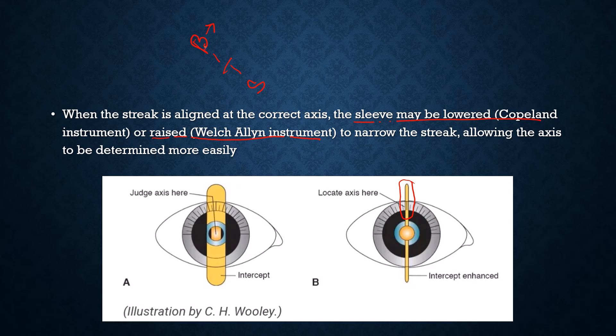To summarize using BITS: there will be no break when the streak is aligned with the reflex; the intensity will be brightest when properly aligned; the beam will be thinnest when nicely aligned; and there will be no skew movement when you are properly aligned with the reflex.